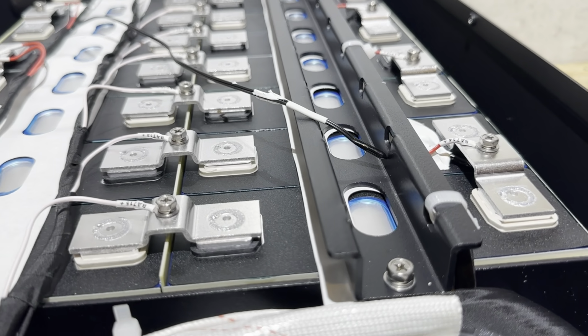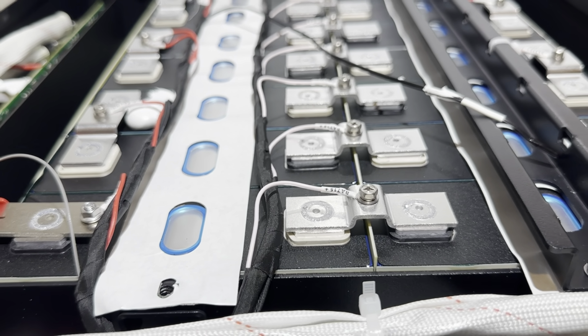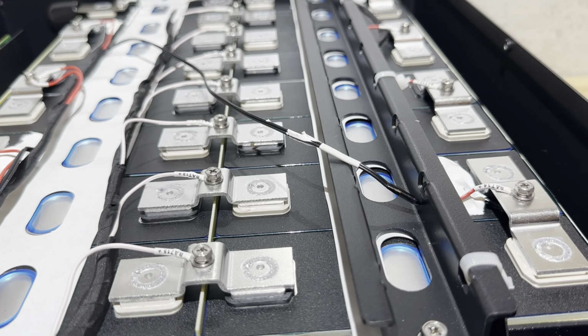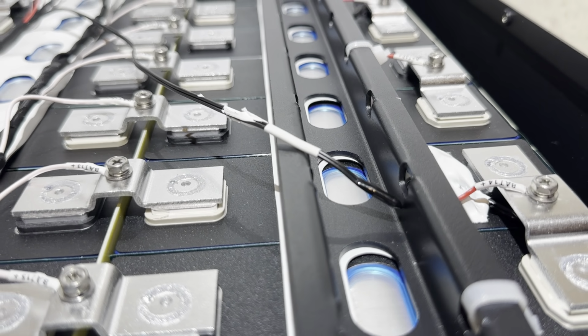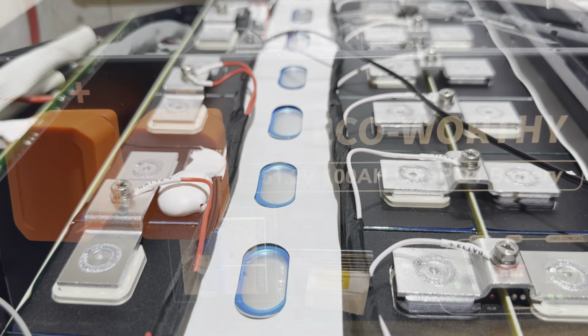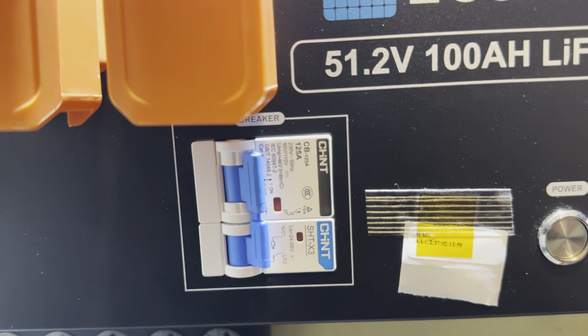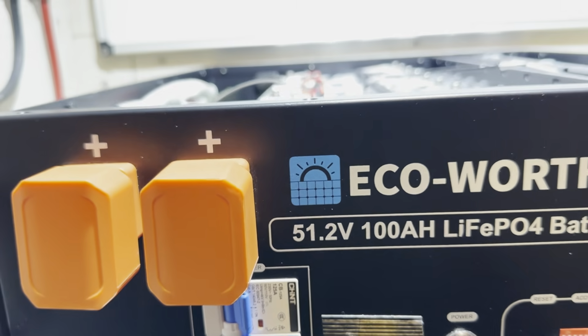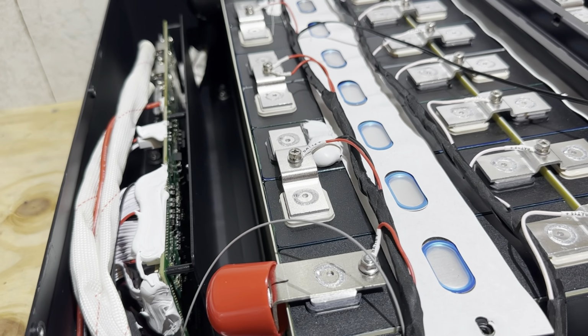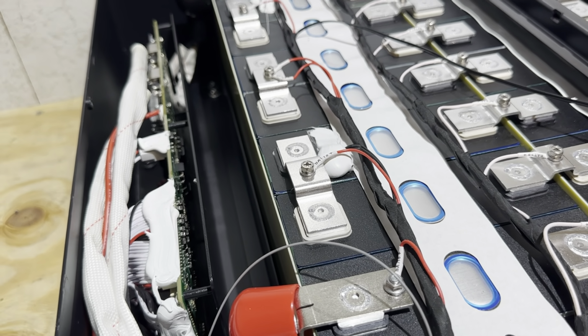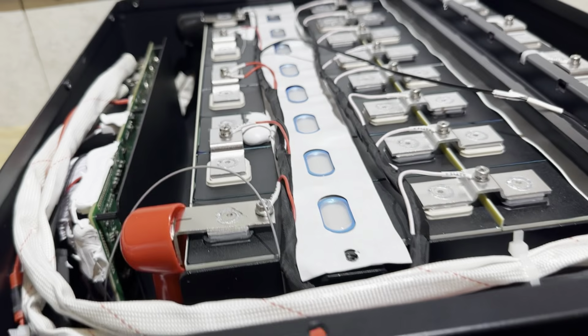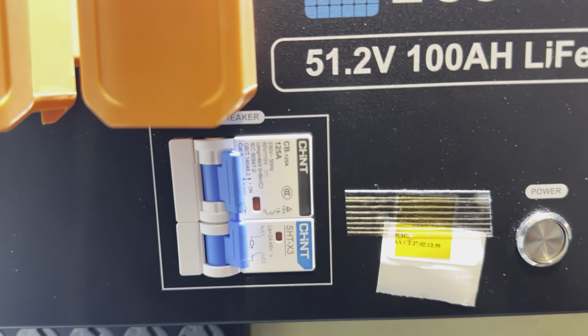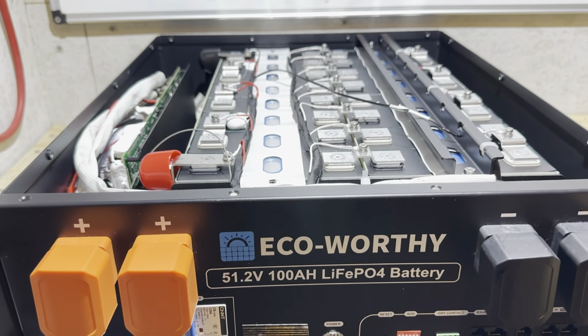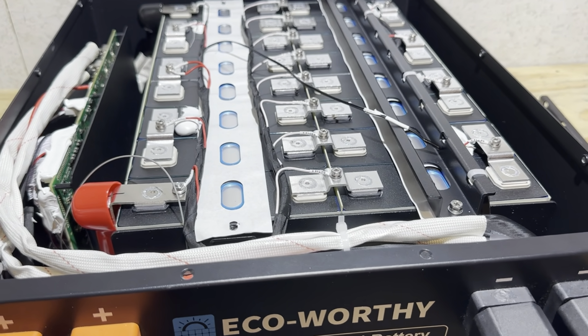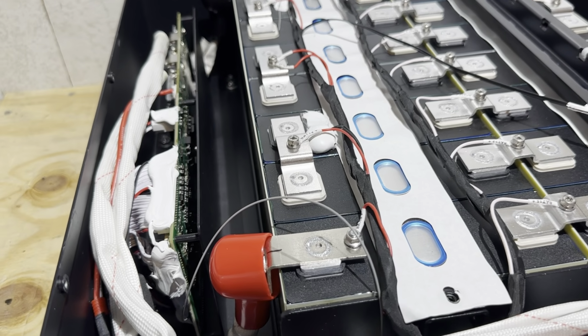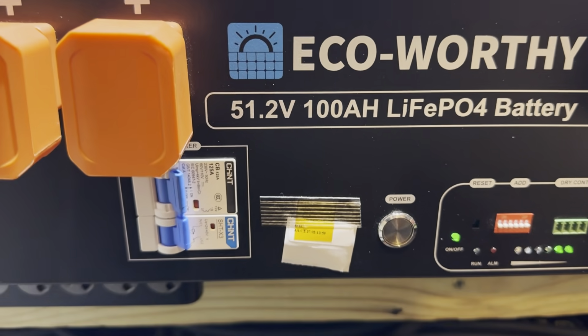And not having the sensors in direct contact with the cell, I mean it was close enough it'd probably not be an issue, but I always like to see the sensors directly contacting the cells for an accurate temperature measurement. Also, I could not get the shunt trip breaker to actually trip and shut off the main breaker. That shunt trip is controlled by the BMS, and I could not find any parameters or specifications of what conditions triggered the BMS to trip the shunt breaker, which actually shuts down the main breaker. I thought a cell low voltage or high voltage condition would have been one of the pre-programmed points. So I'm still researching this board and how to actually make it trip the shunt.